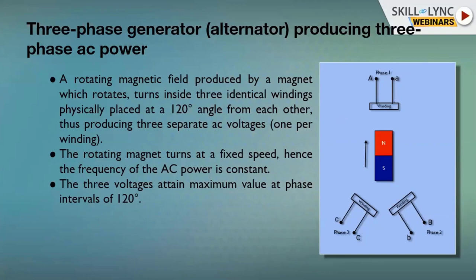The three windings form the stator — the stationary part that does not rotate, and which is also very heavy. A rotor is placed inside. A DC voltage is supplied to the rotor to develop a north pole and a south pole, producing flux. This flux cuts across the stationary stator conductors, inducing an EMF in all three windings.